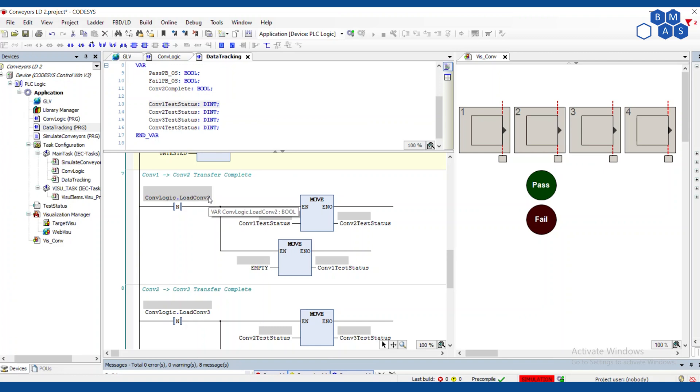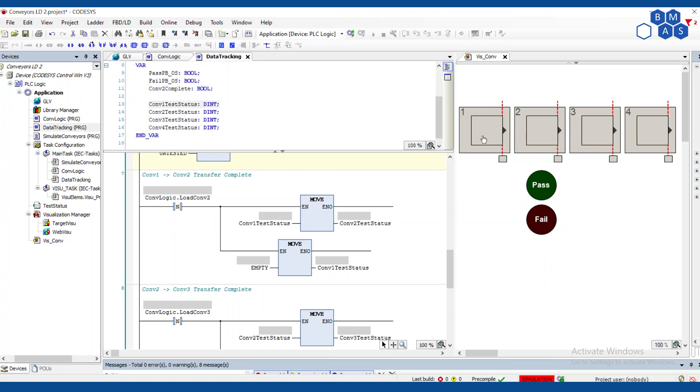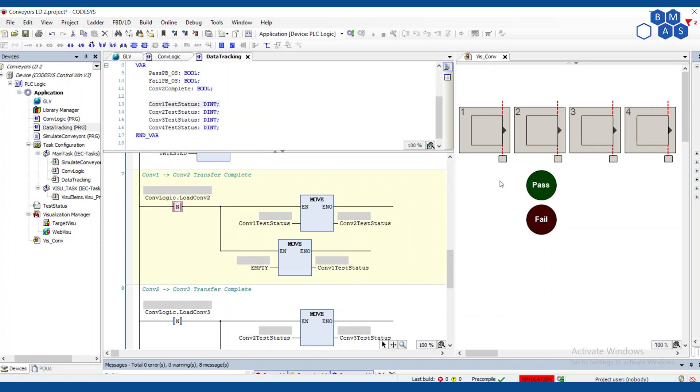And then when we're transferring from conveyor one to conveyor two, we're watching for the falling edge of our internal state load conveyor two. And that means that load conveyor two is complete. Now, depending on how you're tracking the internal state of moving this across, this might get a little bit weird. For example, what happens if that's moving and a sensor flickers? Could the part be somewhere in the middle? What happens if it's moving and an e-stop is pressed? These are all conditions that you're going to have to consider. There's not a one size fits all. So I'm just assuming that this is going to work.